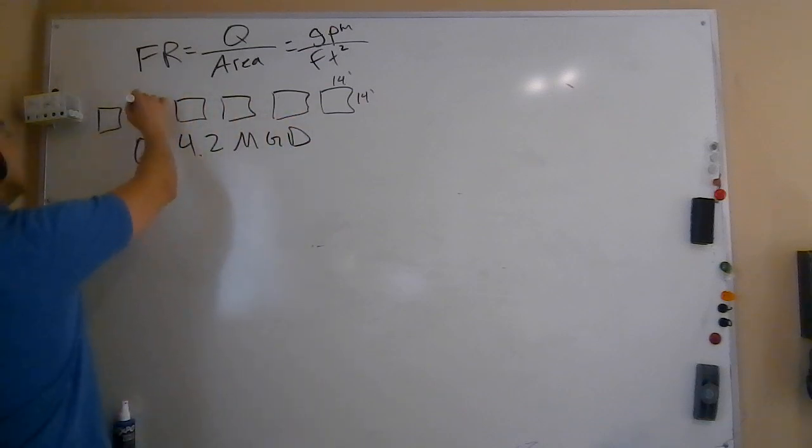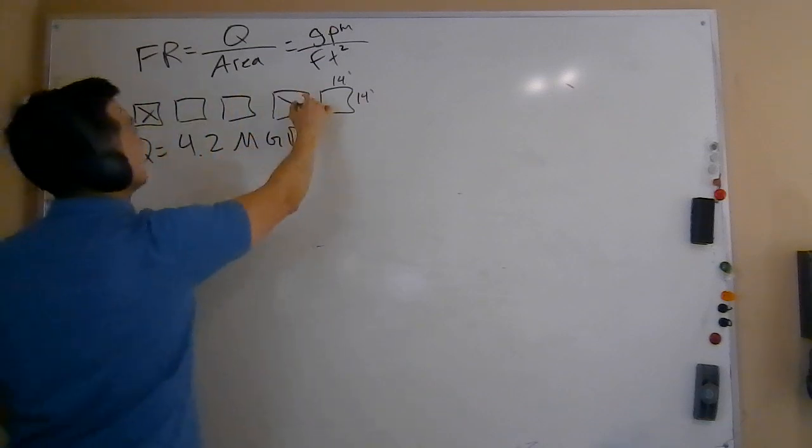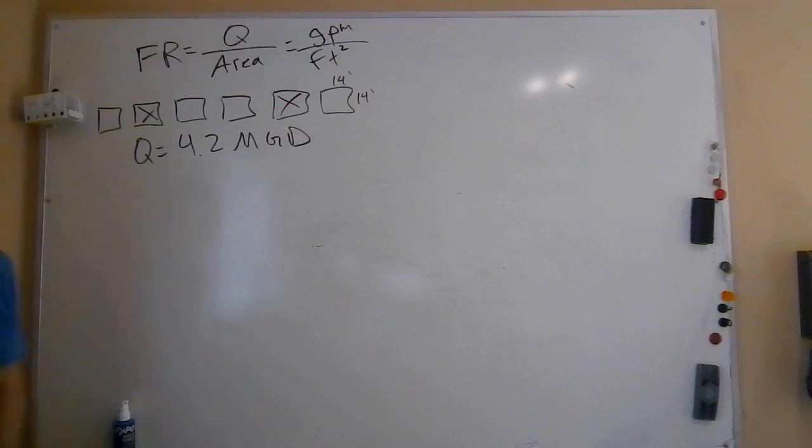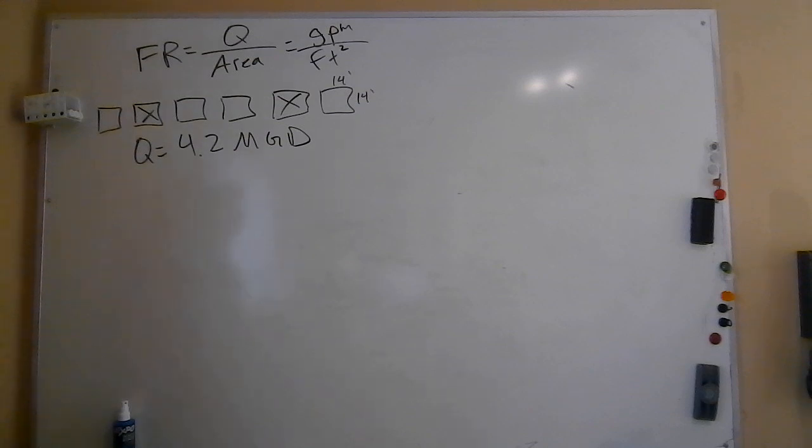Now, right now of the six filters, we have filters two and five offline, whether it's for repairs, routine maintenance, changing filter media, or maybe we just don't need it to treat the size flow that we've got coming in on average right now this time of the year. Either way, we've got four of these filters that are treating this total flow rate of 4.2 million gallons per day. We want to calculate what is the filtration rate across the board here, at least on average amongst the four filters.